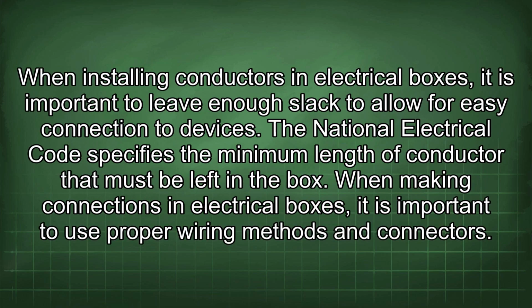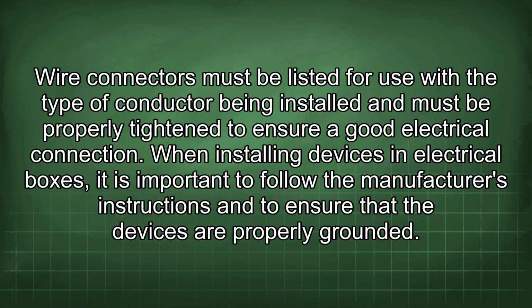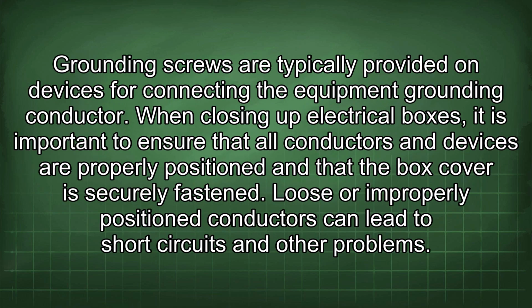When installing conductors in electrical boxes, it is important to leave enough slack to allow for easy connection to devices. The National Electrical Code specifies the minimum length of conductor that must be left in the box. When making connections in electrical boxes, it is important to use proper wiring methods and connectors. Wire connectors must be listed for use with the type of conductor being installed and must be properly tightened to ensure a good electrical connection. When installing devices in electrical boxes, it is important to follow the manufacturer's instructions and to ensure that the devices are properly grounded. Grounding screws are typically provided on devices for connecting the equipment grounding conductor.